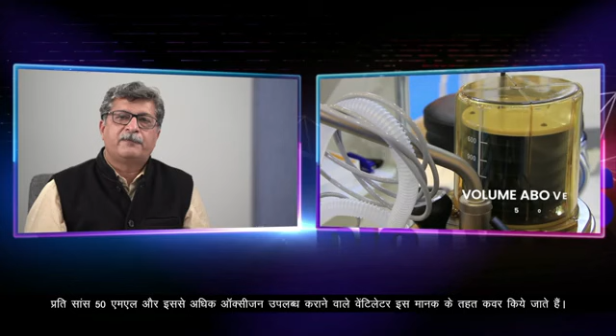Ventilators intended to provide a delivered volume up to 50 ml per breath, and those intended to provide a delivered volume above 50 ml per breath, are covered in this standard. The standard mandates that the ventilator shall be equipped with oxygen monitoring equipment with an inbuilt alarm system for the measurement of inspiratory oxygen concentration. Such a ventilator shall be capable of supplying gas to the patient containing an oxygen concentration over the range from ambient to at least 90%.